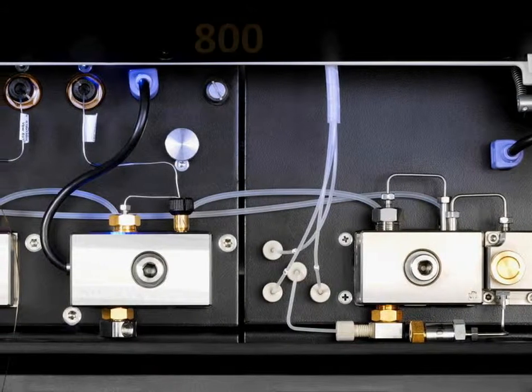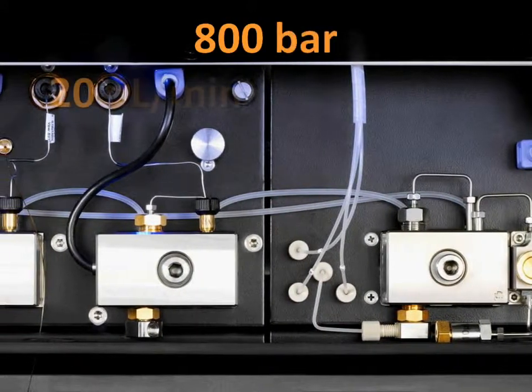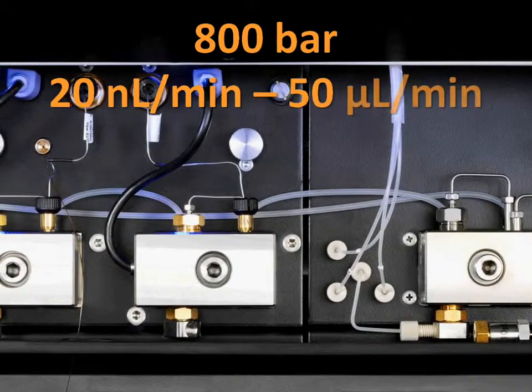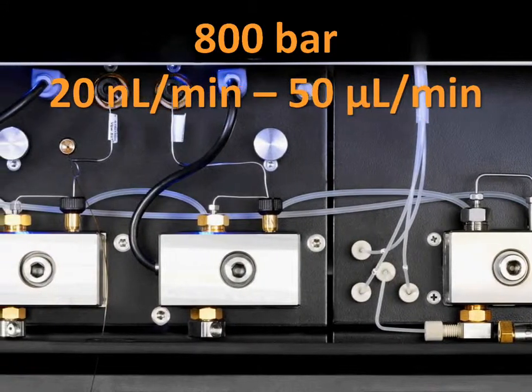The RSLC nano can run at pressures as high as 800 bar across flows from only 20 nanoliters per minute up to 50 microliters per minute.